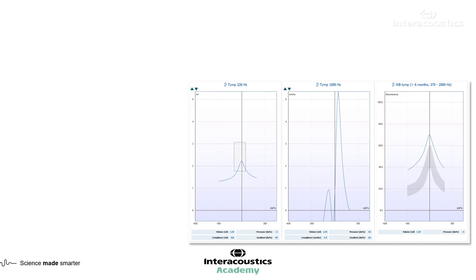Let's have a look at the tympanograms page. In the left ear, the wideband average tympanogram is higher up the graph than the normative area. That's an indication that there is more energy being absorbed, in particular at the higher frequencies. When we look at it relative to the 226 Hz probe tone, because we're looking at additional frequencies, we get a bit clearer picture of that. There's something we need to pay attention to here.